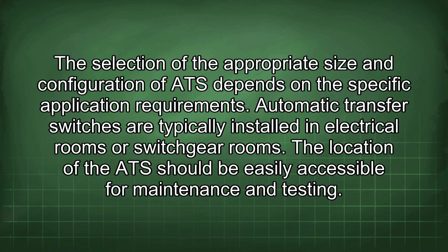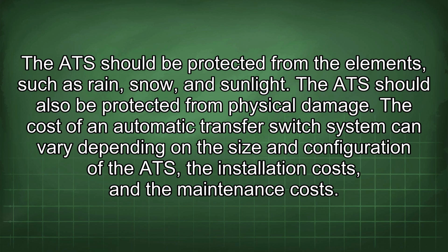Automatic transfer switches are typically installed in electrical rooms or switchgear rooms. The location of the ATS should be easily accessible for maintenance and testing. The ATS should be protected from the elements such as rain, snow, and sunlight. The ATS should also be protected from physical damage.